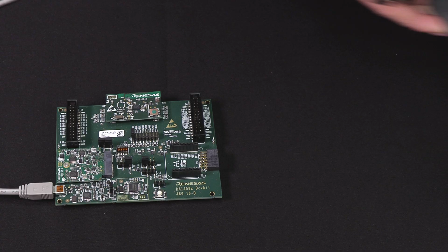Before we start taking measurements, we need to perform a calibration to verify and adjust the accuracy of the module's readings by comparing them to reference measurements. The circuit accuracy is measured by applying a constant current, monitoring the same current with an external instrument and the ADC of the PMM2 module, then comparing the two. In general, the inaccuracy presented in the current measurement circuit is less than 5%, which is practically less than 2% in most of the current range.